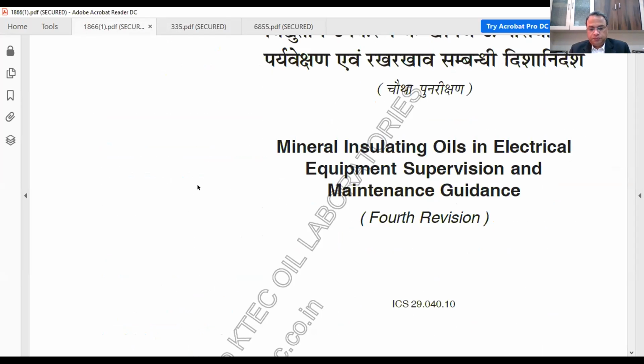If you want to test transformer oil which has not been used in a transformer, in that case we need to refer to IS 335. The oil which has been used in a transformer, which we have already poured into the transformer, after filtration, in that case IS 1866 we have to follow.